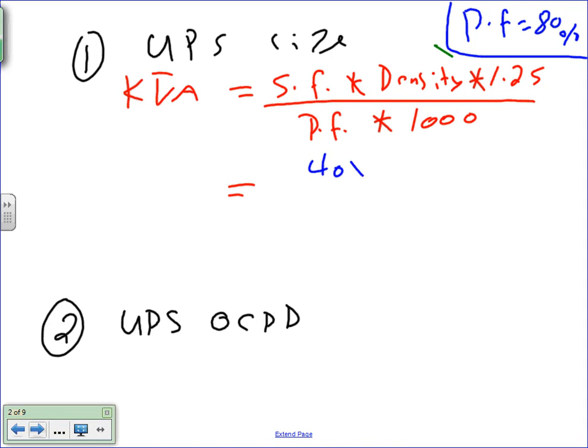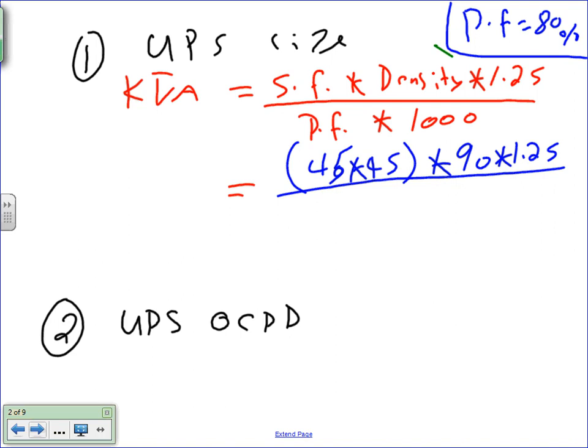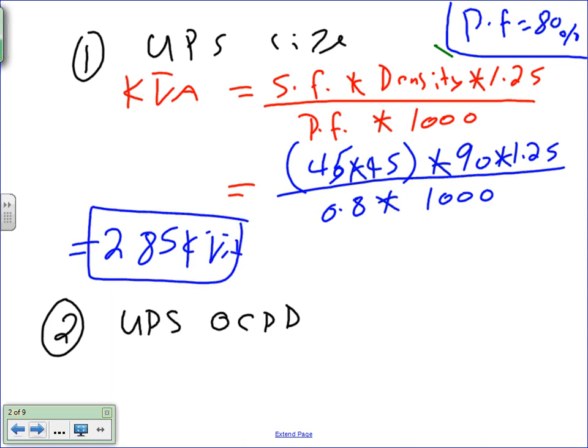So I have a 45 times 45, that's the area, multiplied by the power density, which is 90, multiplied by 1.25, to accommodate for losses in the whole system. I know it might be exaggerated a little bit. Power factor 0.8, and divide by 1,000 to convert into kVA. When you do all this math, you're going to end up with, I believe, 280. If you do this, you're going to end up with 285 kVA. Okay?